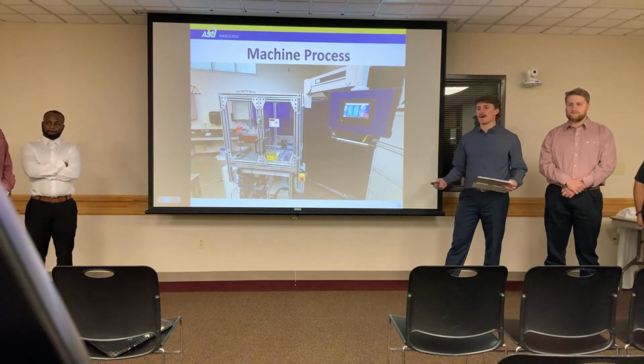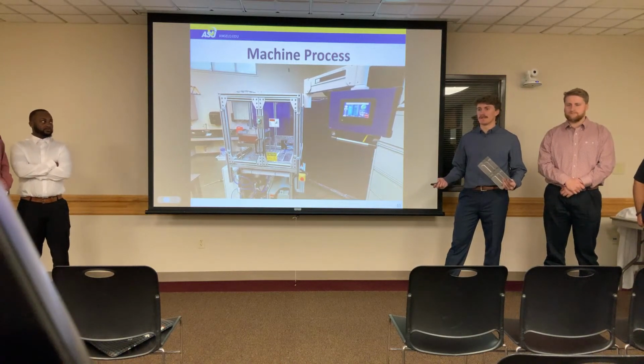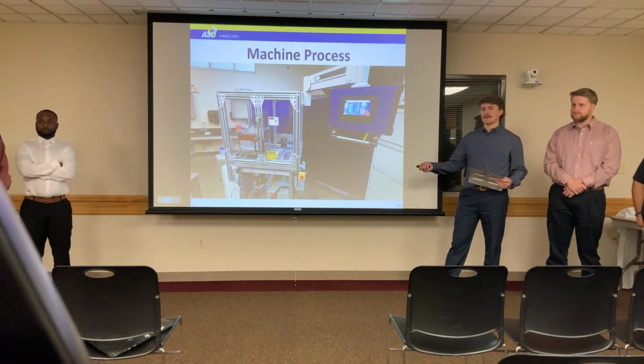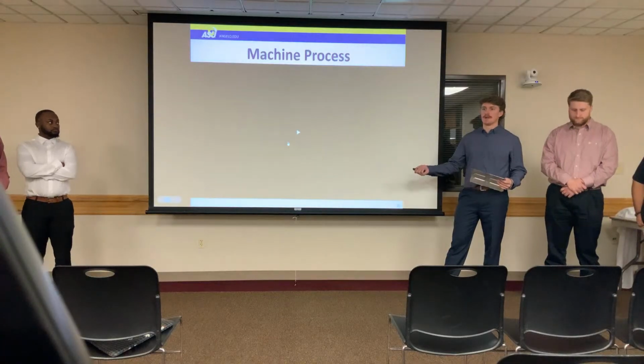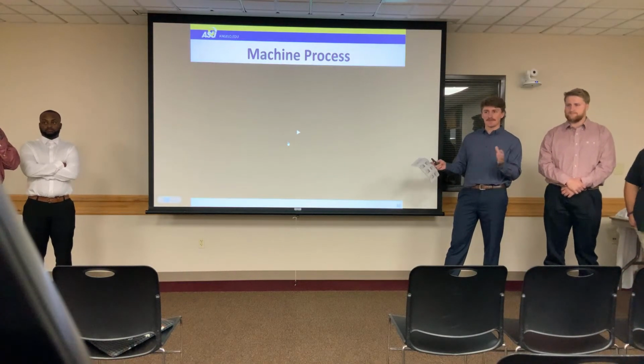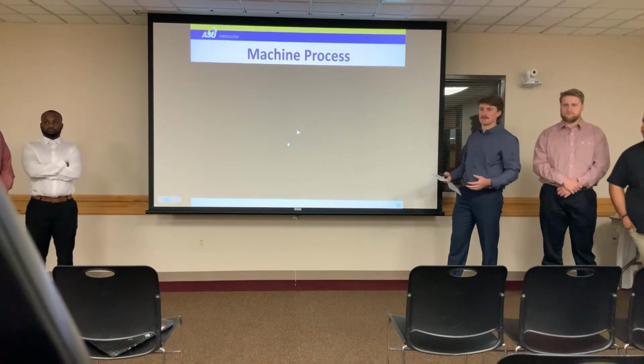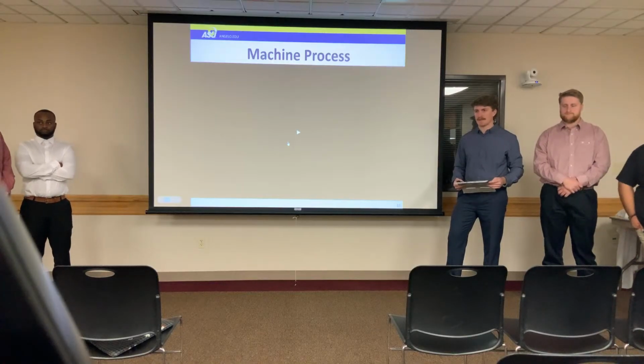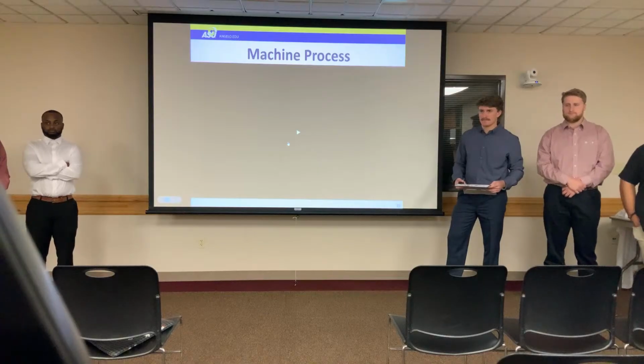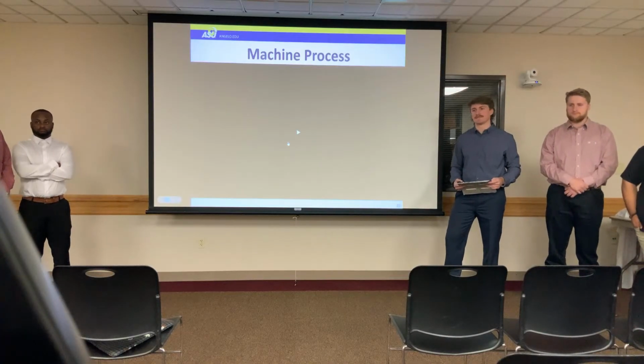Right, so we're calibrating to the best of our ability, given the engineering units, we plugged into the machine and set offset values to scale it to the validated actual reading. So if it's producing 0.3 millivolts, it's supposed to read 75 pounds, but you weren't putting 75 pounds on the end and checking it. No, that's right, just simulating it. Yep, it's a simulation calibration.